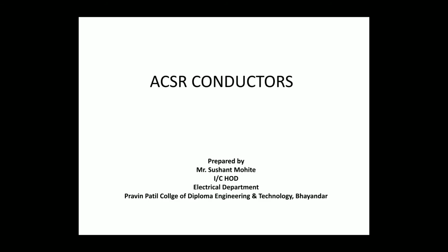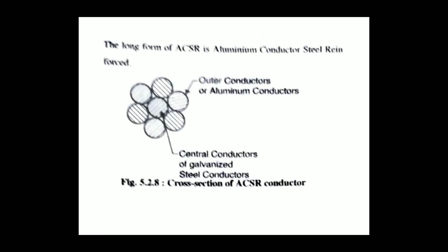Then very important is the ACSR conductor. At the time of transmission, the important factor is the mechanical strength. The mechanical strength of copper, aluminium, all aluminium conductor and all aluminium alloy conductor is very less. So here we use the ACSR conductors. The full form of ACSR is aluminium conductor steel reinforced.